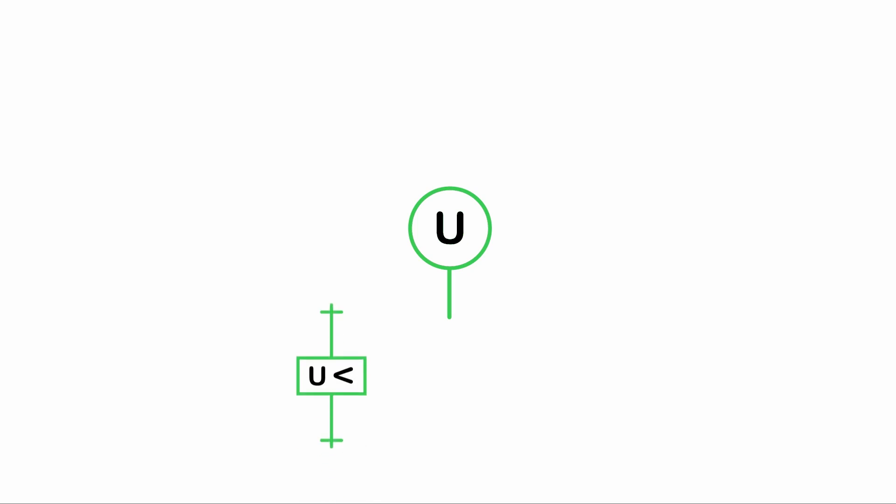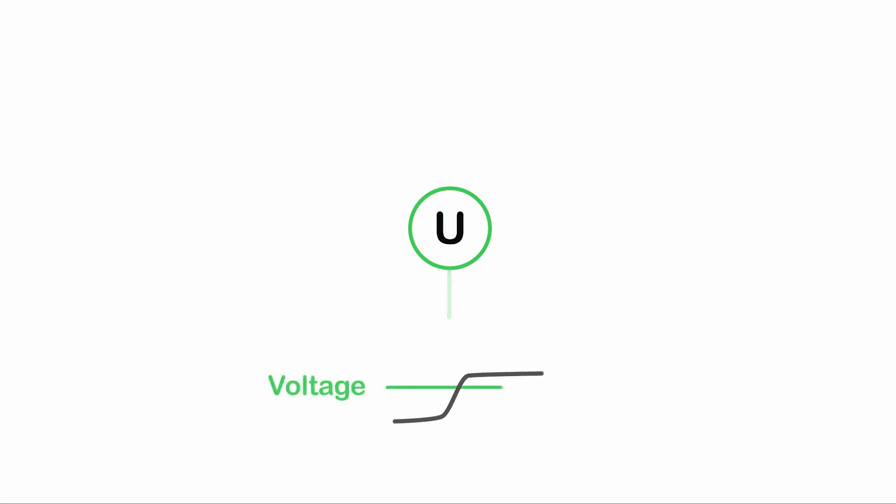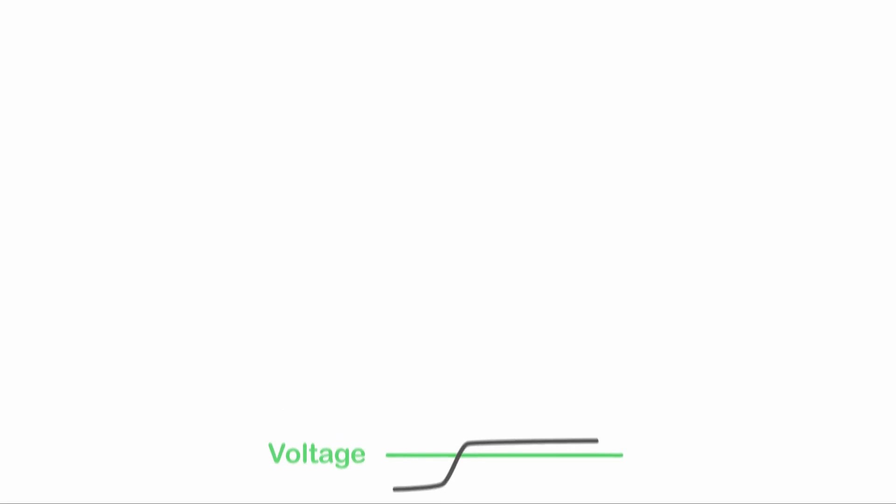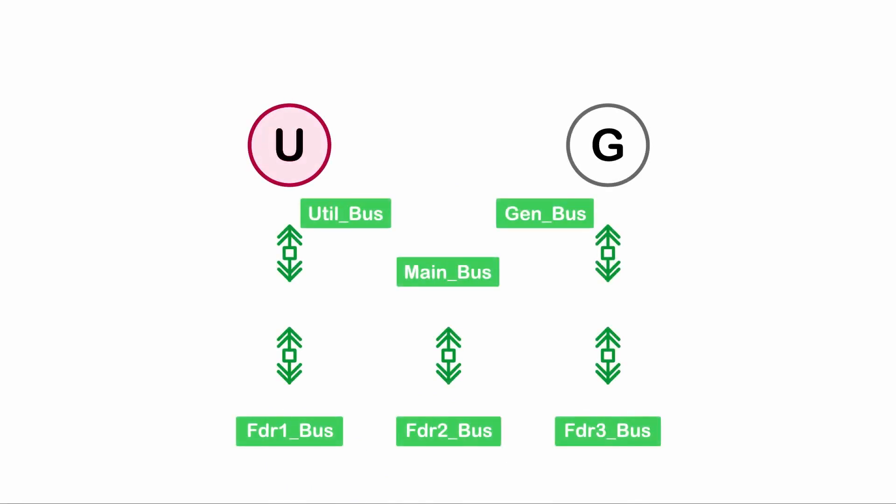Ideally, this active condition will be a fixed indicator, like an undervoltage relay is off or a generator is running. However, we can also trigger on analog conditions, such as voltage being over a certain level. In either case, the source is what sets the color of the bus it is attached to. The sources can all have the same color, or we can use different colors to quickly identify which source is energizing a piece of equipment.